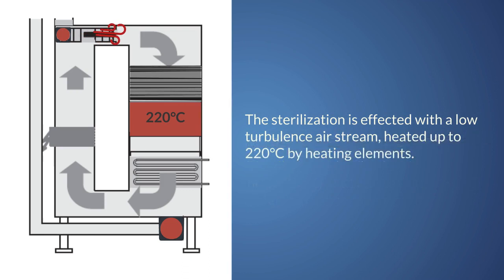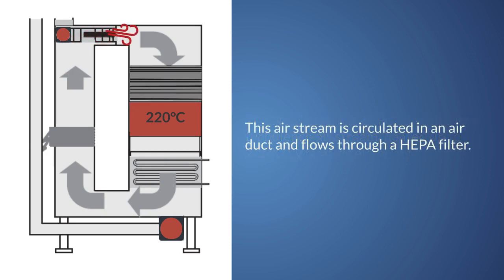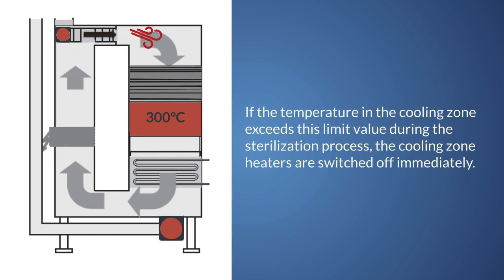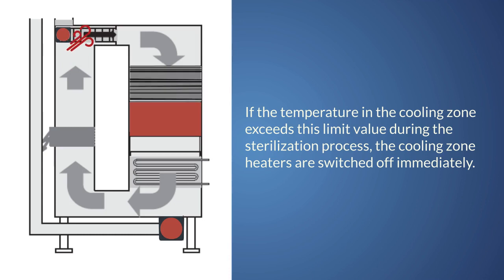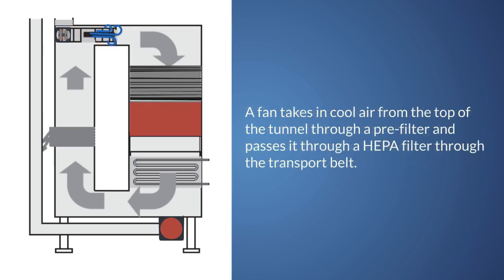The sterilization is effected with a low turbulence airstream, heated up to 220 degrees Celsius by heating elements. This airstream is circulated in an air duct and flows through a HEPA filter. If the temperature in the cooling zone exceeds this limit value during the sterilization process, the cooling zone heaters are switched off immediately. A fan takes in cool air from the top of the tunnel through a pre-filter and passes it through a HEPA filter through the transport belt.